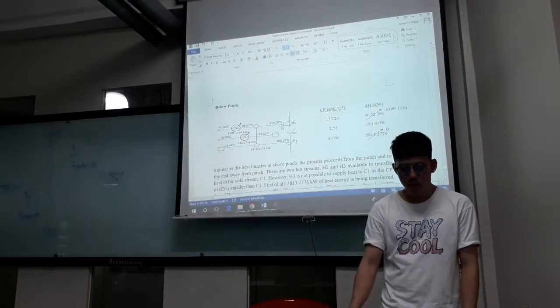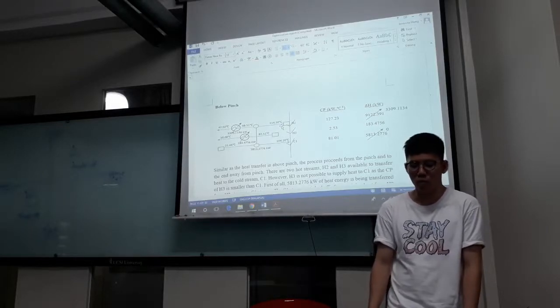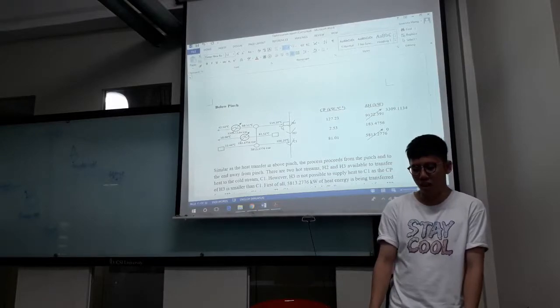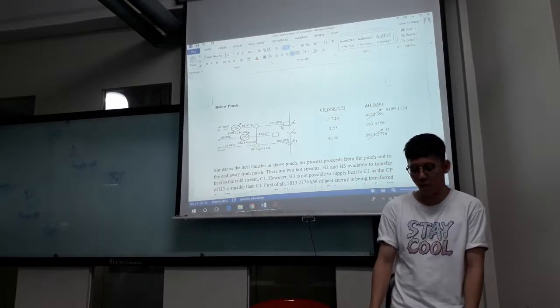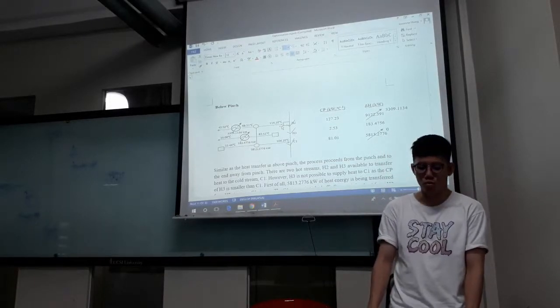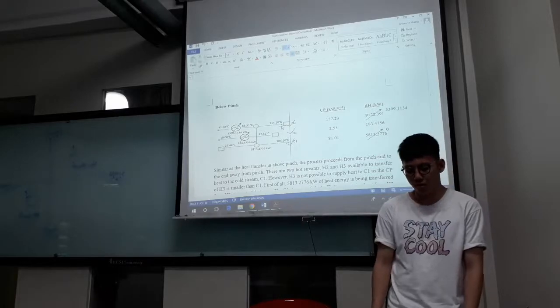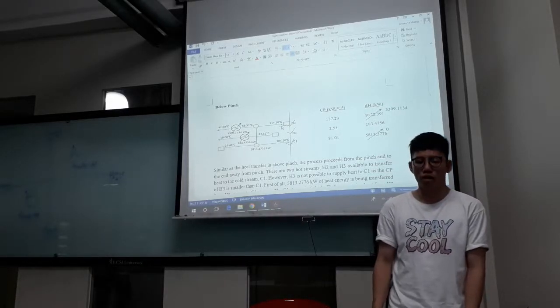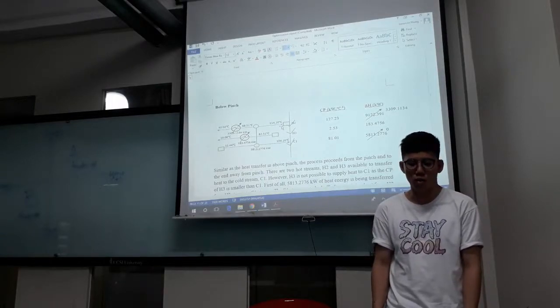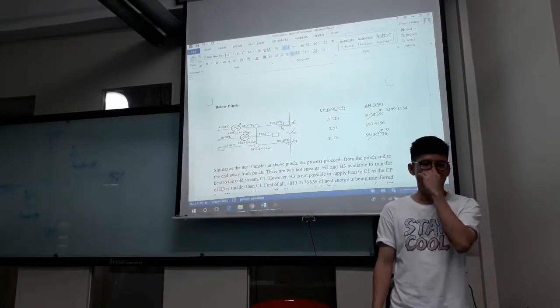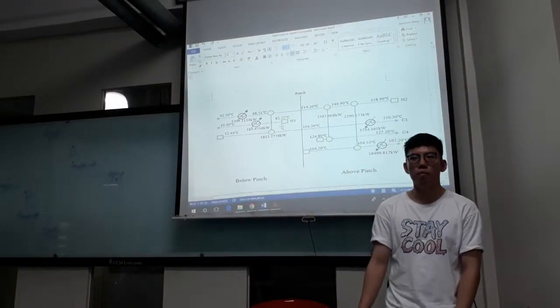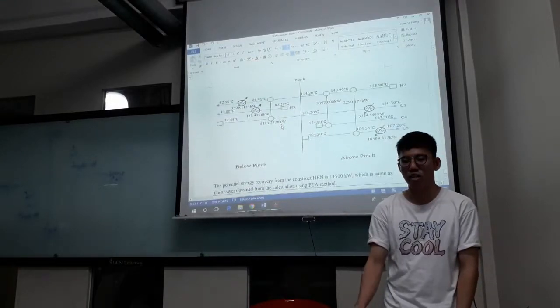Then we move to the below-pinch section. At the below-pinch, we follow the CP inequality rules as well. Here we have 2 hot streams which can provide energy to C1. However, H3 cannot provide heat to C1 because its CP is lower than C1's, which violates the rules. So the energy from H1 is transferred to C1, and C1's energy is fully recovered and taken off. The remaining H2 energy and H3 energy are then removed by 2 coolers. The below-pinch HEN is also complete.